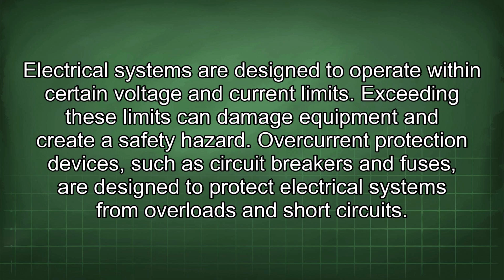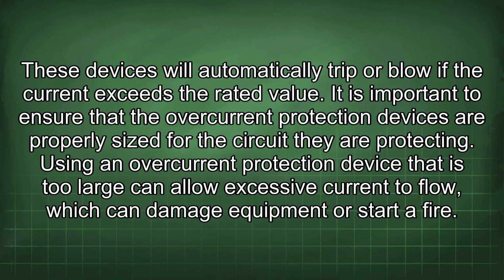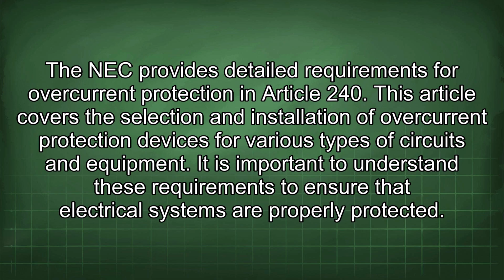Overcurrent protection devices, such as circuit breakers and fuses, are designed to protect electrical systems from overloads and short circuits. These devices will automatically trip or blow if the current exceeds the rated value. It is important to ensure that the overcurrent protection devices are properly sized for the circuit they are protecting. Using an overcurrent protection device that is too large can allow excessive current to flow, which can damage equipment or start a fire. The NEC provides detailed requirements for overcurrent protection in Article 240. This article covers the selection and installation of overcurrent protection devices for various types of circuits and equipment. It is important to understand these requirements to ensure that electrical systems are properly protected.